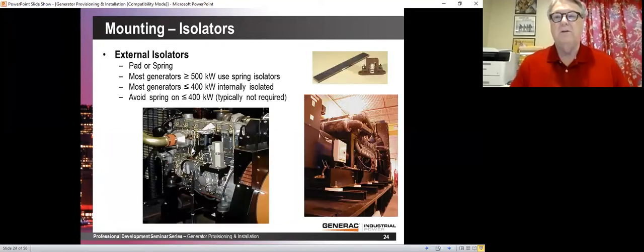Here's isolators. This is one of my pet peeves. We get specifications from engineers that specify that they want springs under the generator. Well, where do you put those springs? You can't put them between the tank and the generator because that's all custom designed. There's no room to put them there. And that is where the manufacturer will have isolators, but you can't put more springs there. So we have to put them under the tank.